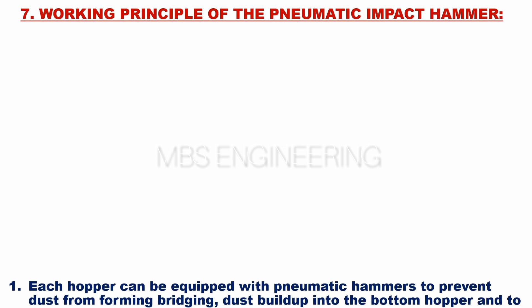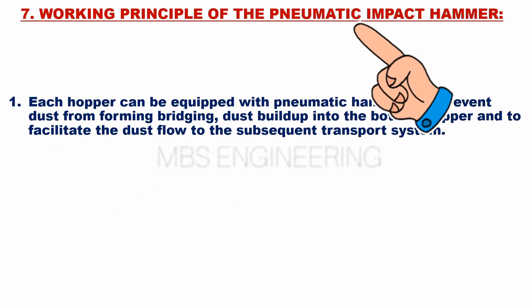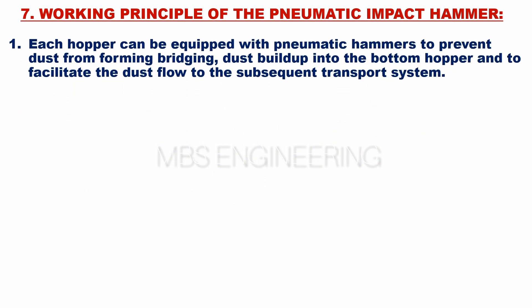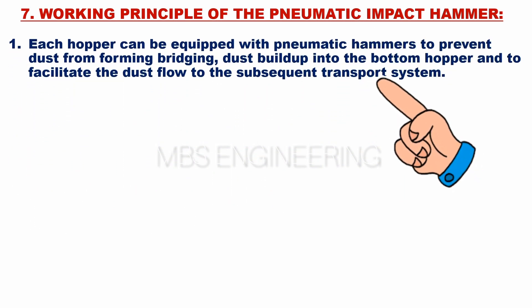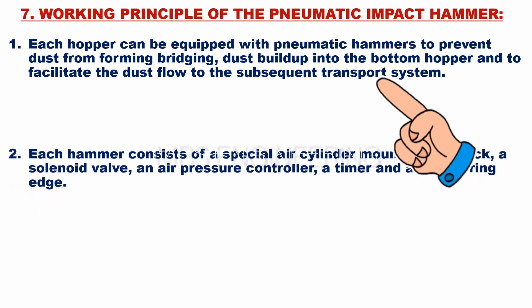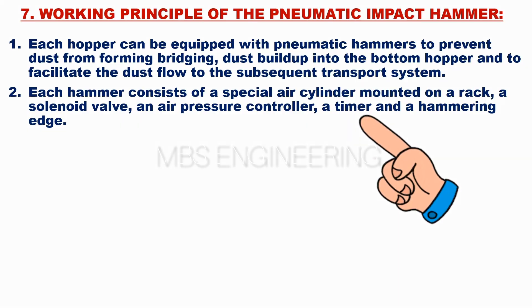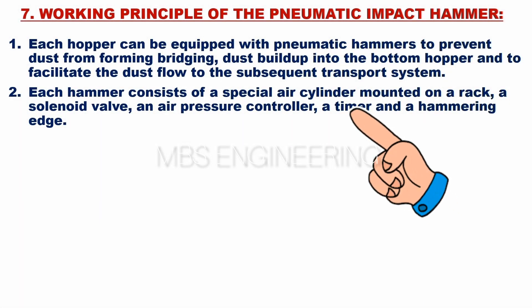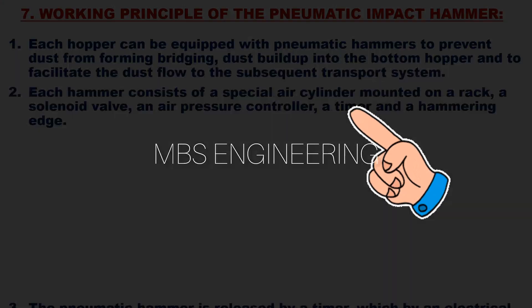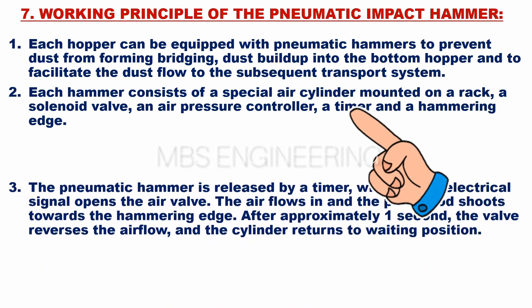The working principle of the pneumatic impact hammering system: each hopper can be equipped with pneumatic hammers to prevent dust from forming bridges, reduce dust buildup at the bottom hopper, and to facilitate dust flow to the subsequent transport system. Each hammer consists of a special air cylinder mounted on a rack, a solenoid valve, an air pressure controller, a timer, and a hammering edge.